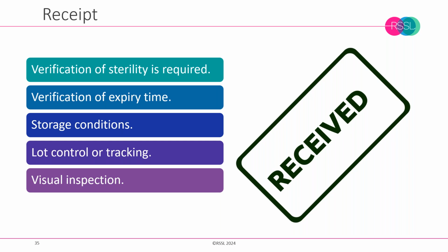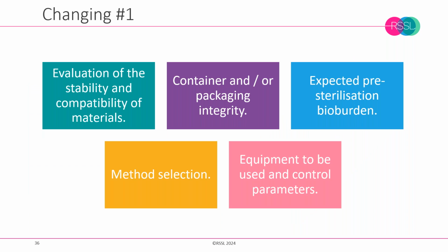So there's lots of things to weigh up, and this makes the change control process quite important. So if we're introducing a new item, or if we are changing part of the material or design, or we're altering the sterilisation method, and particularly with all of those where there is product contact, we need to take everything through change control. And for our change control evaluation, we need to have an understanding of the stability and compatibility of the materials, an understanding of the container or package integrity. We need to know what our pre-sterilisation bioburden is, and the confidence that our sterilisation method can effectively deal with that, and what our control parameters are going to be.